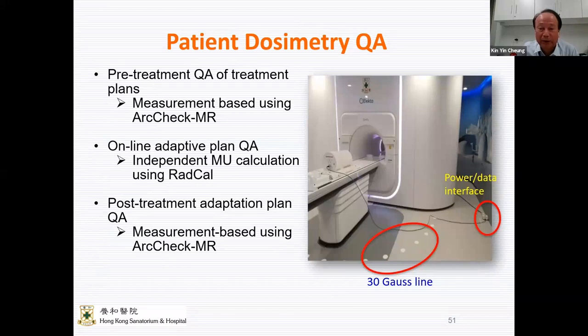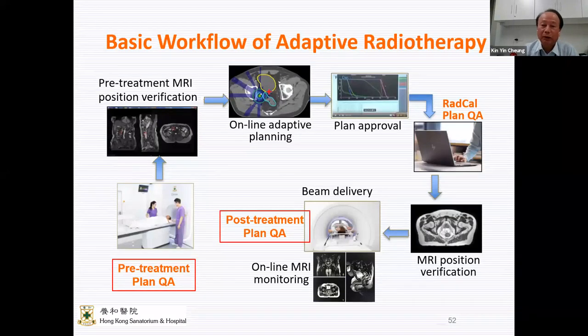For patient dosimetry, based on measurement, we want to do a complete end-to-end measurement for every case using ArcCheck. So all pre-treatment QA are done using ArcCheck. But during adaptation therapy, perhaps I show you this workflow diagram of a typical treatment workflow. Before treatment, we have to do a pre-treatment plan QA using ArcCheck.